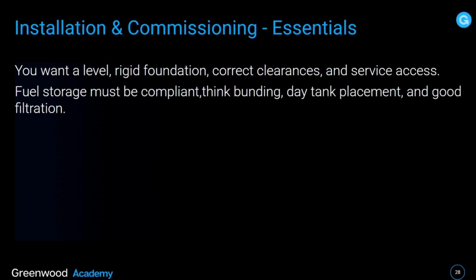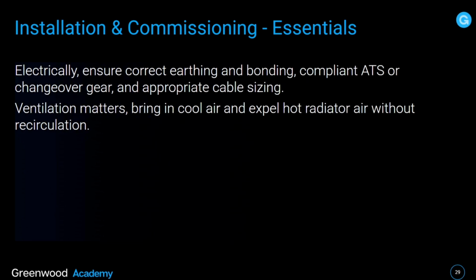When it comes to actually installing the genset, you really require a level, rigid foundation with correct clearance and service access. It's really important. And fuel storage must be compliant. Think bunding, day tank placement, and good filtration. Fuel filtration is incredibly important. Electrically, ensure correct earthing and bonding, a compliant ATS or changeover gear, and appropriate cable sizing. Now, ventilation matters, so you need to bring in cool air and expel hot radiator air without recirculation.